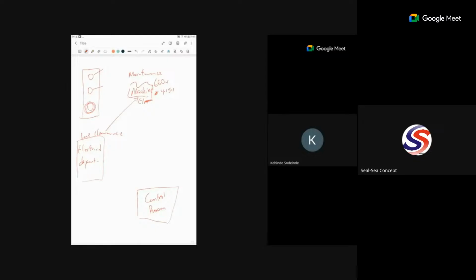He said no. If you've worked with them before, you know line clearance isn't needed, just do it fast. My friend then told him, okay, there's a provision for an emergency switch. When you press this emergency switch on the plant, the control room won't be able to start that machine. What they'll see on their system is an error, until someone comes back to release the emergency switch.